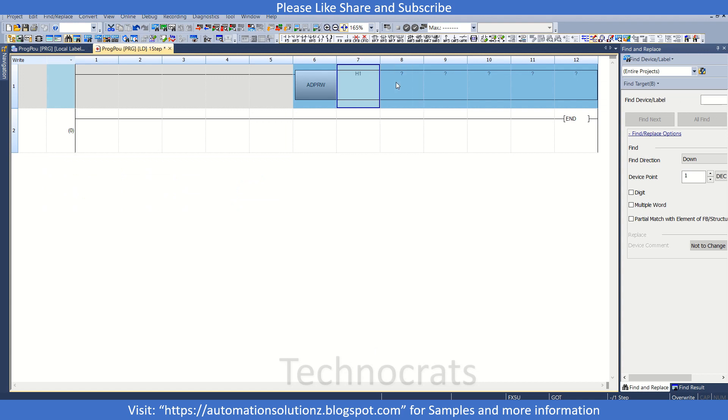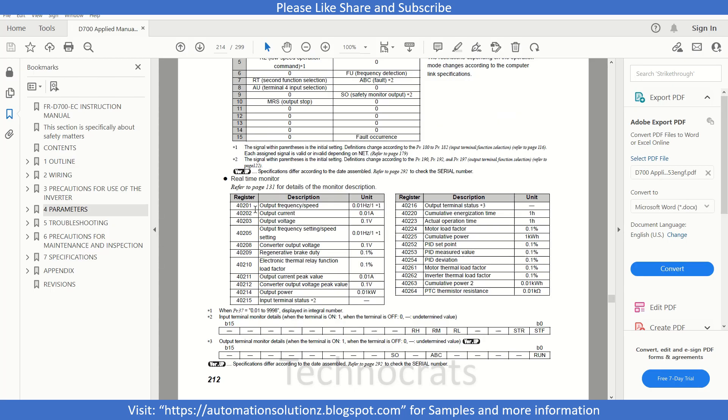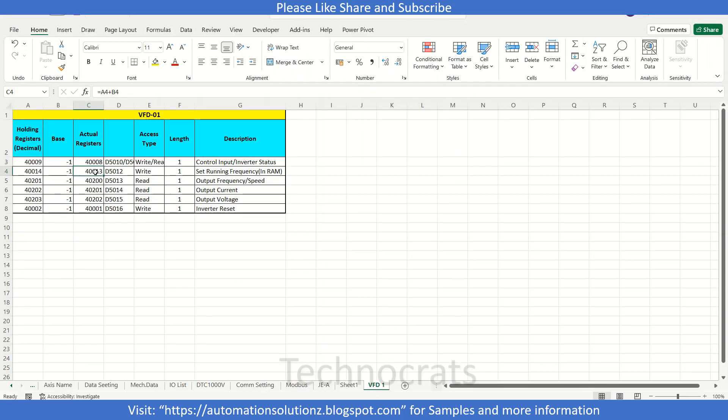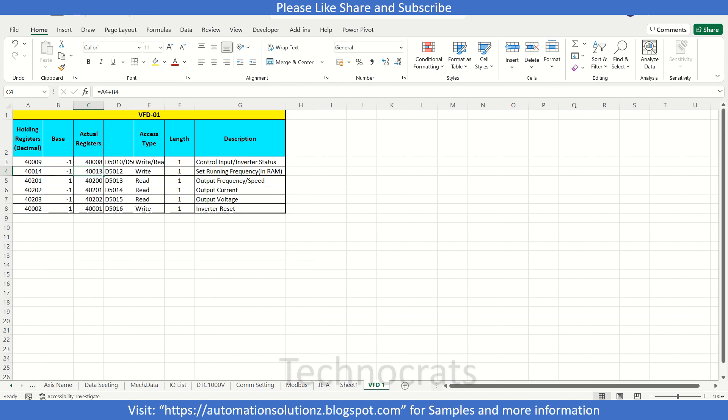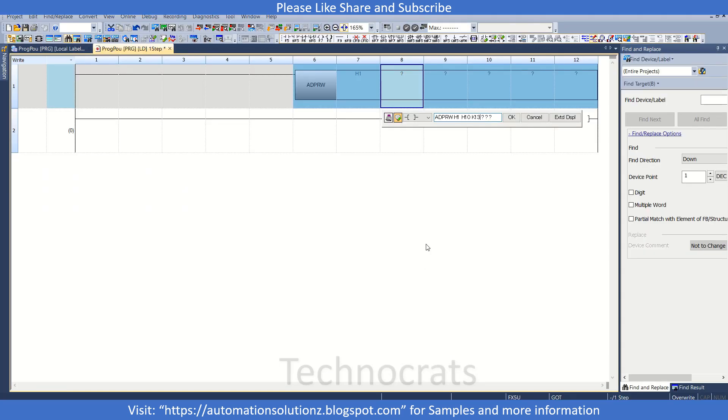Let us write it in our program. Our slave address is H1. Now we will use H10, that is our function code. Then 13, that is your Modbus address as mentioned here. So 13 we will use here as a Modbus write address.